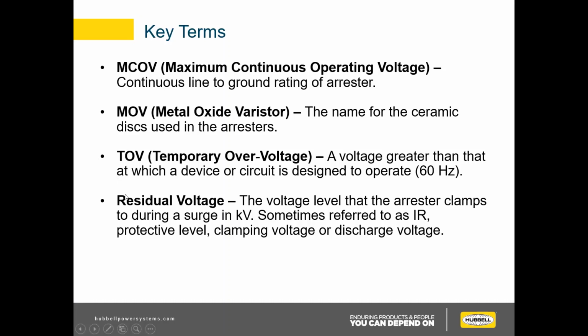And then residual voltage, and this is pretty synonymous to many things, but this is the voltage level that the arrestor clamps to during a surge in kV. So it can be referred to as IR, protective level, clamping voltage, and discharge voltage. You'll hear me say all of those throughout the presentation.